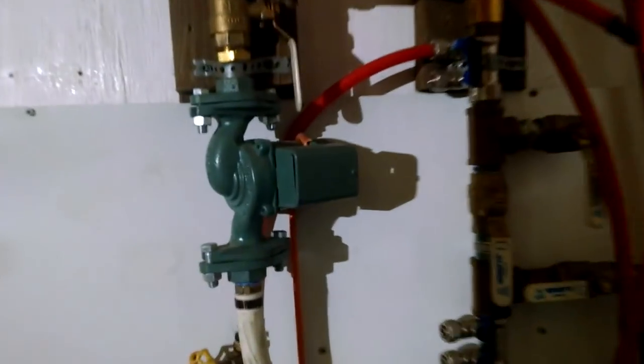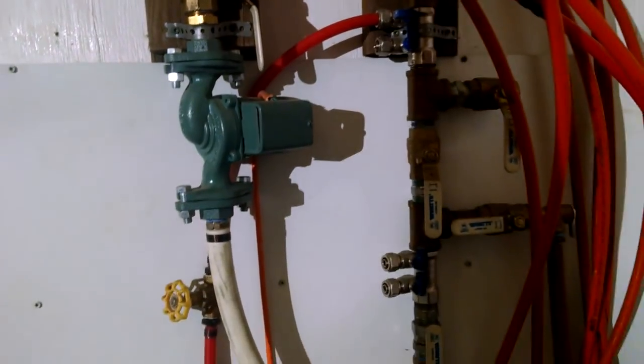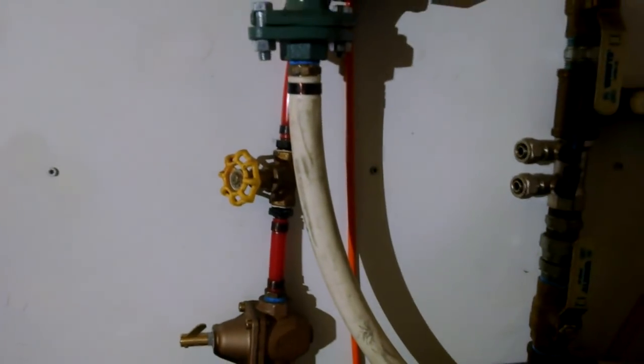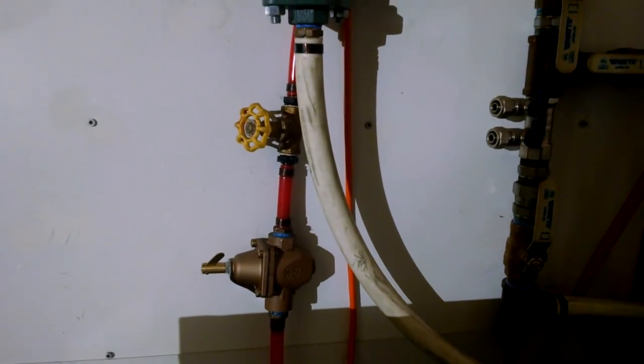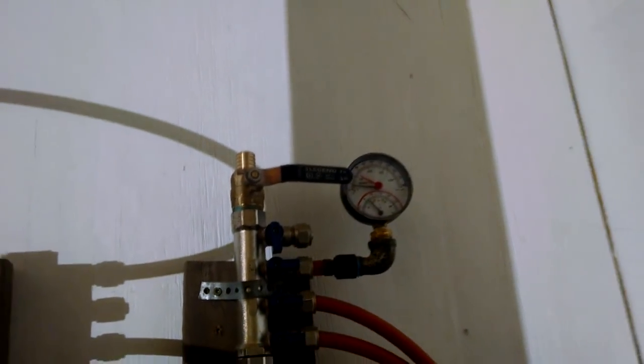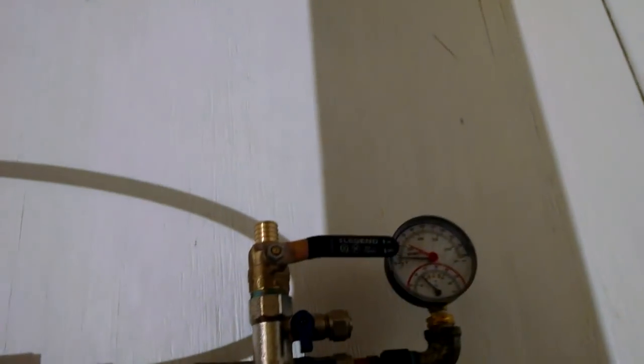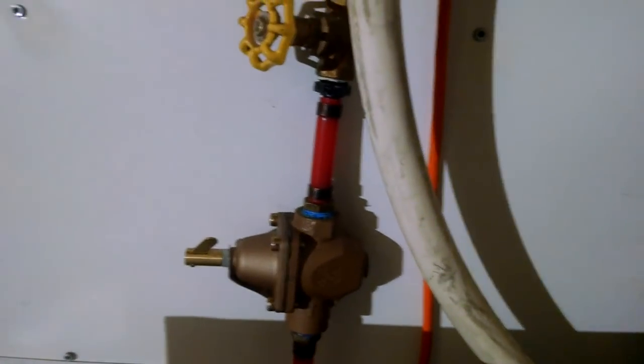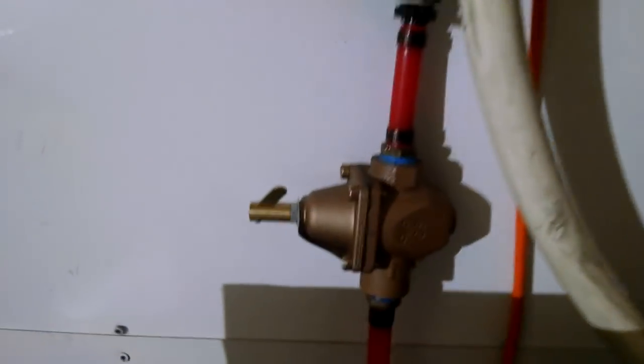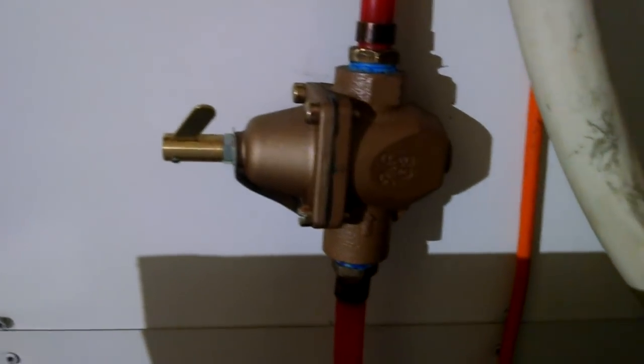So right now the pump is pumping here. To start the system, you fill the system with water. Here's a fill valve, and then check for leaks. Get all the air out. The air is purged out when you're filling. This is actually our air purge on the forward line, so we can just open that up to let air out. But the priming procedure is very tricky actually, and this valve here, pretty much indispensable.